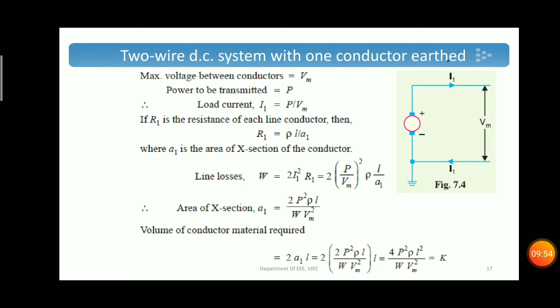As we have seen, P square rho L square by W Vm square is written as K. Here it is equal to K by 4. That means while we are using a two-wire DC system with midpoint earth, the volume of conductor required is 1 by 4 times the volume of conductor required in a two-wire DC system with one conductor earthed.